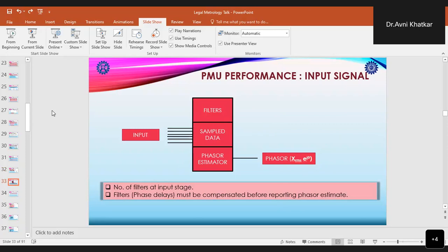Now, after giving the inputs to the PMUs, they are sampled, and a number of filters are used at the input stages. These filters sometimes cause phase delays. So along with these filters, some compensators are also used, so that any phase delay introduced by the filters is compensated before reporting any phasor estimate of the PMU. So after giving the inputs, we get output in the form of a phasor, which has an RMS magnitude along with an angle.